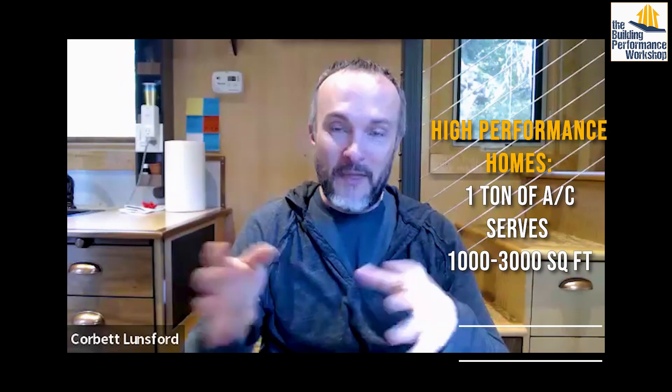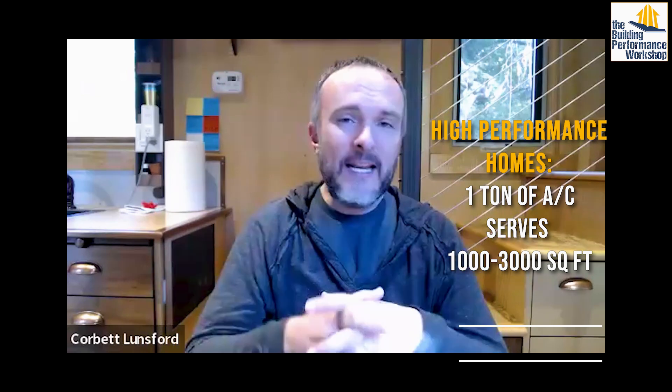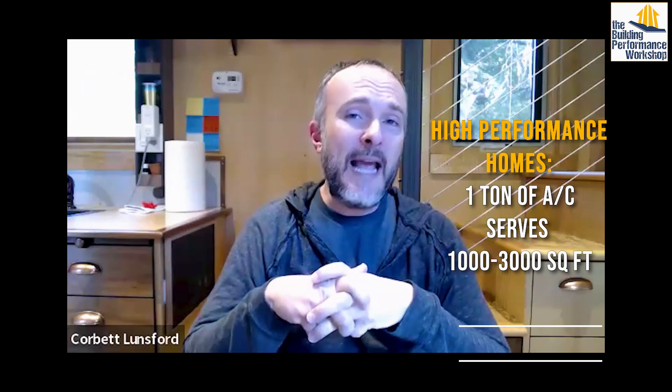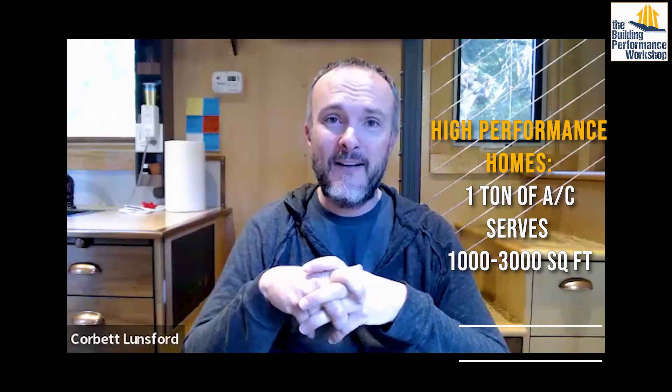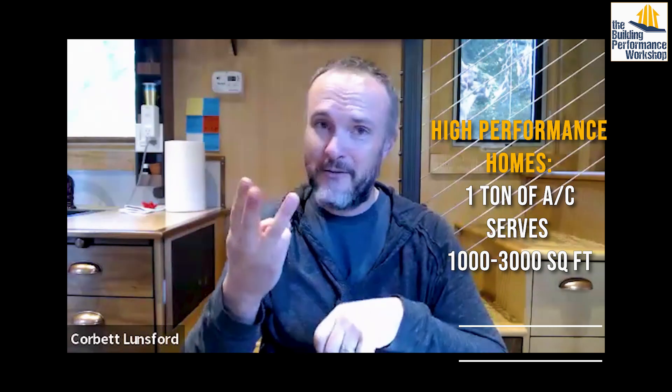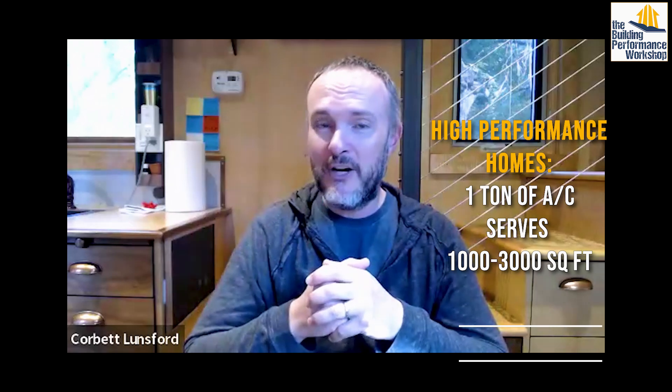The first thing we should do is try and find out how big the total capacity for the entire house needs to be. Often what we find is that not only should we not have four systems because that's ridiculous, but three systems is probably too much because with a high performance home, you're going to end up something like two and a half or even two tons, and trying to split two tons into three parts isn't really going to work.